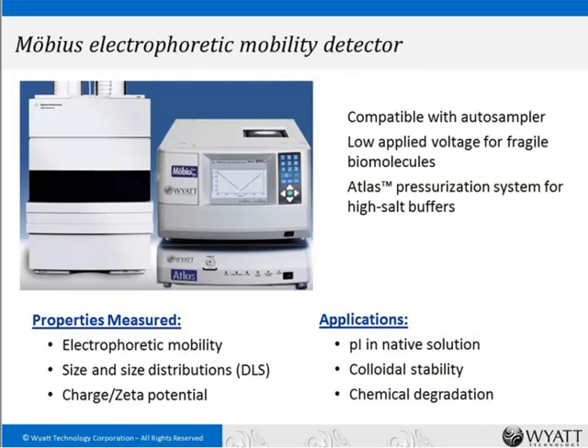Another tool for interpreting interactions is the MOBIUS, an electrophoretic mobility detector that measures zeta potential and net charge on molecules, as well as size and size distributions via integrated DLS. The MOBIUS is compatible with autosamplers so you can load samples and run overnight. It is highly sensitive and works with low applied voltage to avoid damaging samples. You can also incorporate the Atlas pressurization system to overcome bubbles that form during electrophoresis and interfere with measurement.